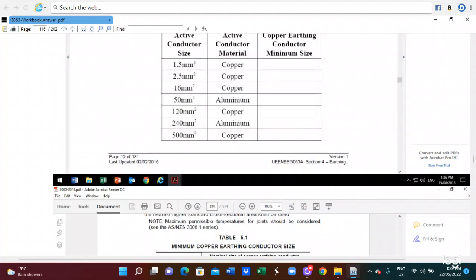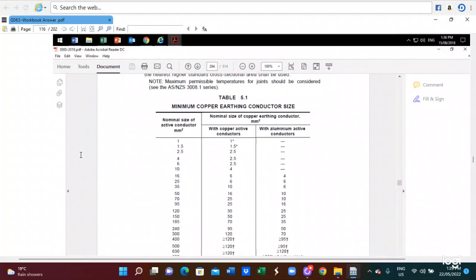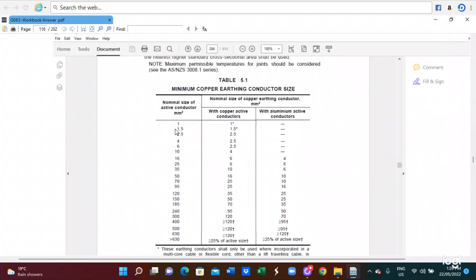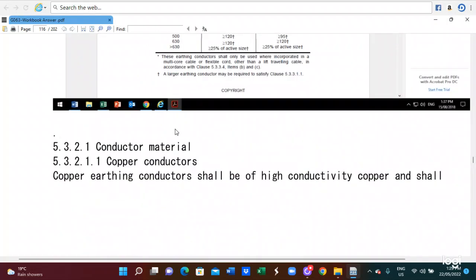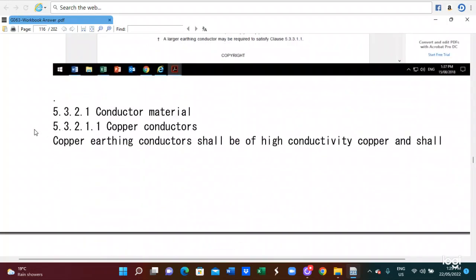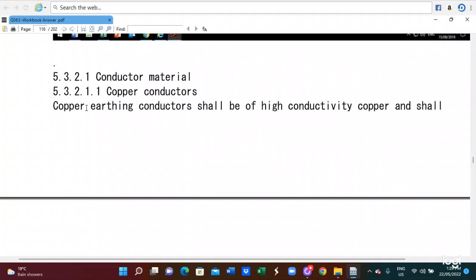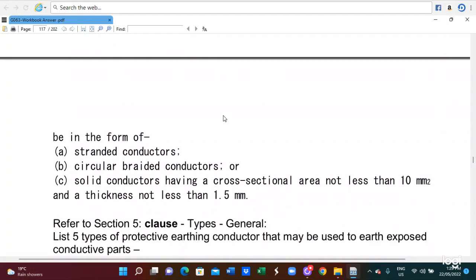Also that you have to read table 5.1, minimum earthing conductor size. Copper earthing conductor size, you can get from table 5.1 or the AS3000. Conductor material, you refer to 5.3.2.1.1 copper conductors.